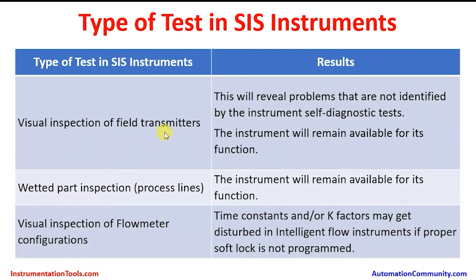Visual inspection of field transmitters: this will reveal problems that are not identified by the instrument self-diagnostic tests. The instrument will remain available for its function — it will not be taken out of service but will continue providing protection. Only the visual inspection will be performed, keeping the instrument in running condition.